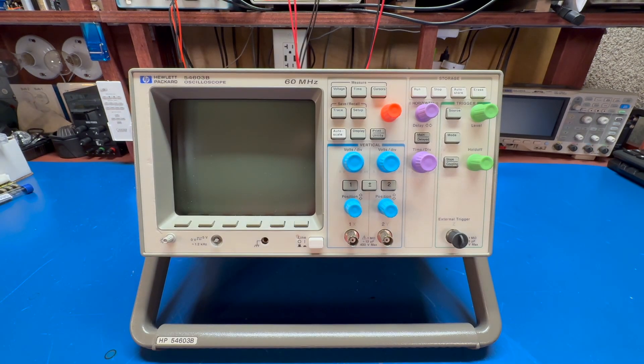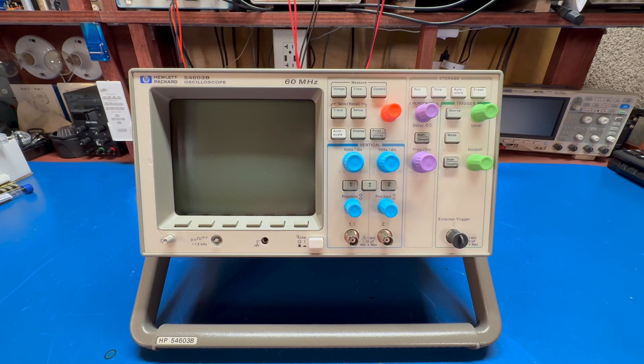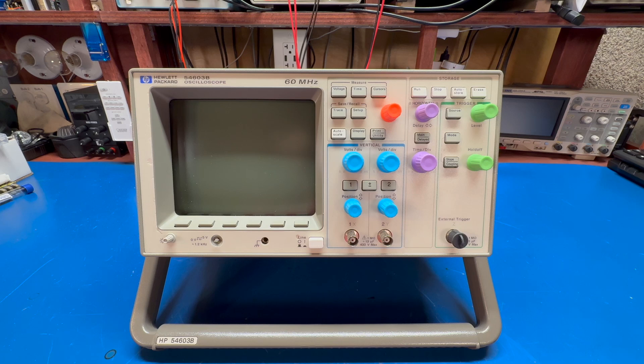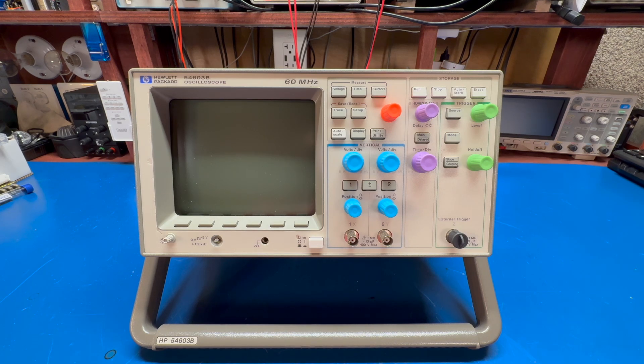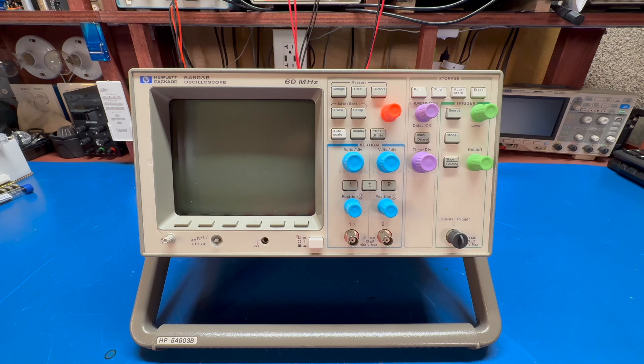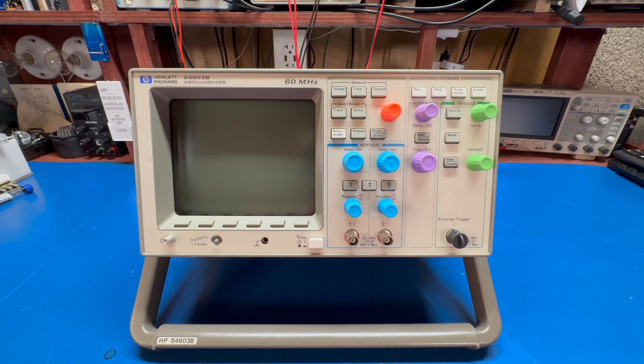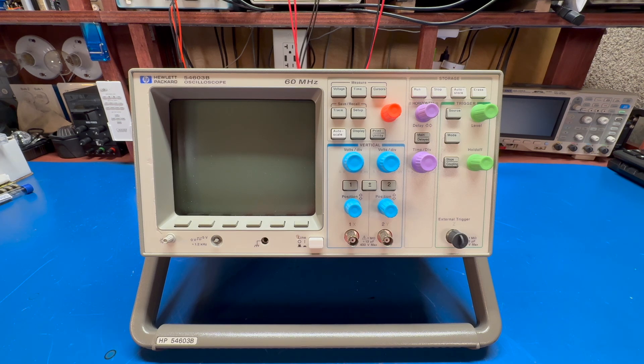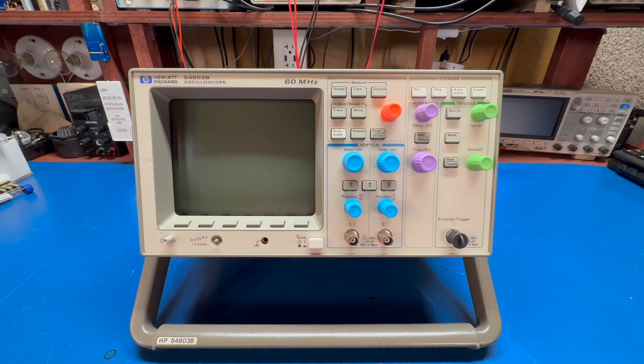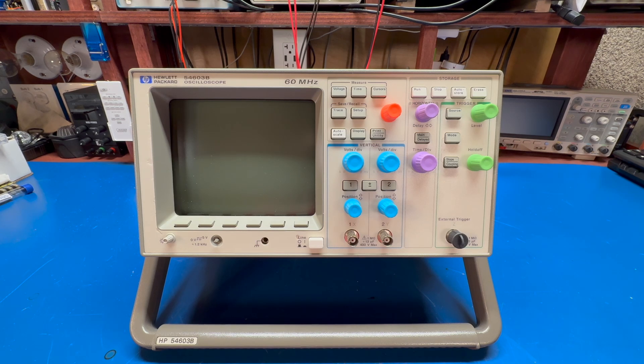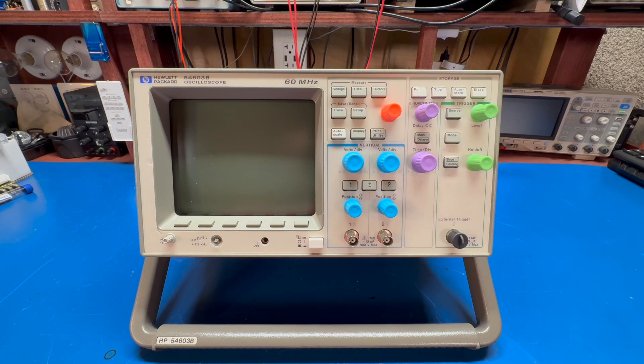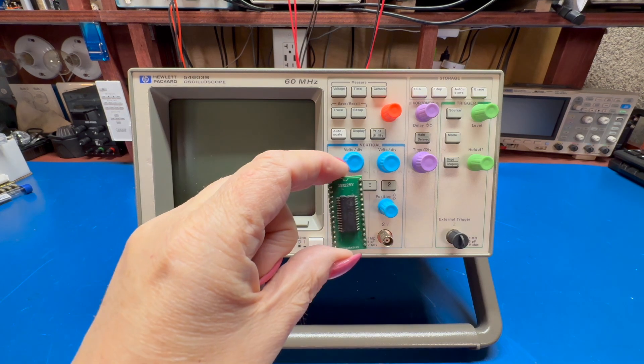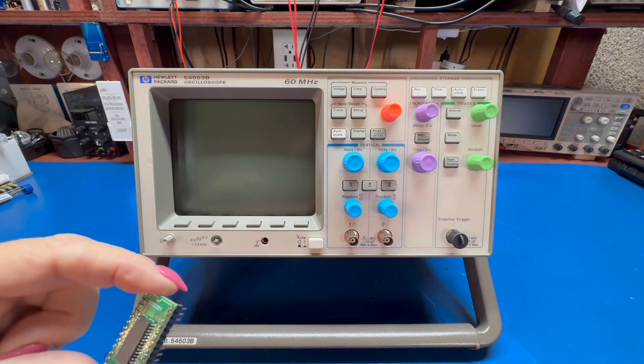It's what these old HP scopes use to store calibration settings. The problem is as those NV RAMs get old, batteries wear out, they weaken, at some point they die, and then there's just nothing you can do. There are ways to cut open the NV RAM chip, solder a battery onto it, and those work, but we can do better.